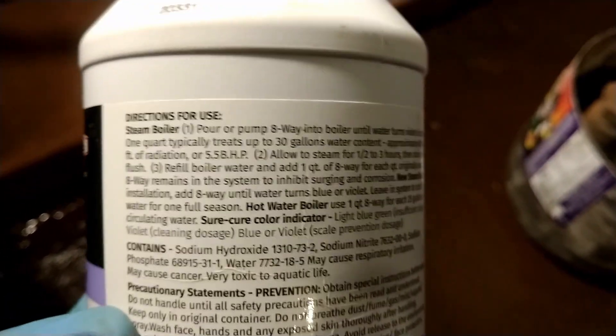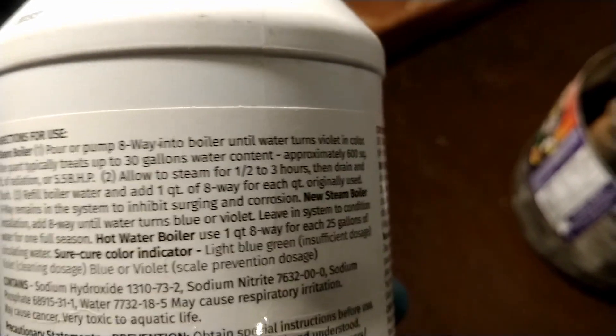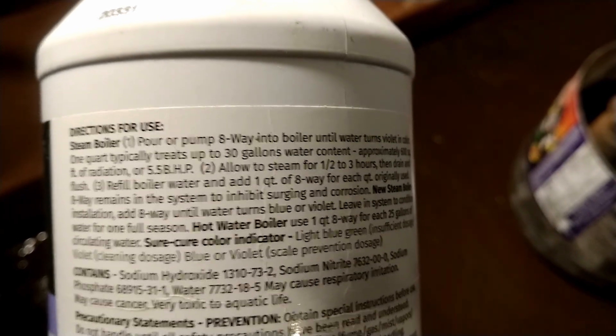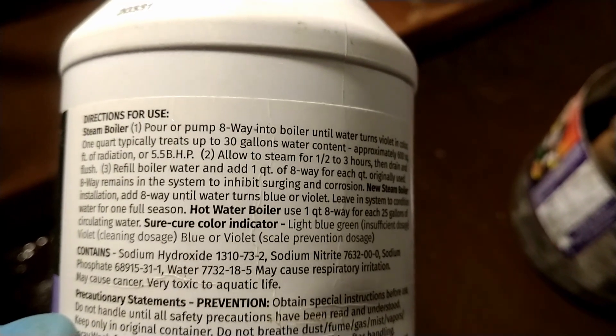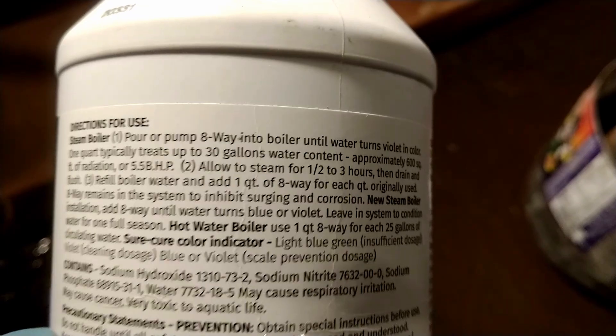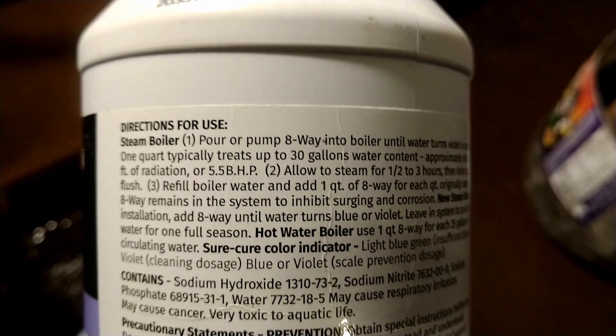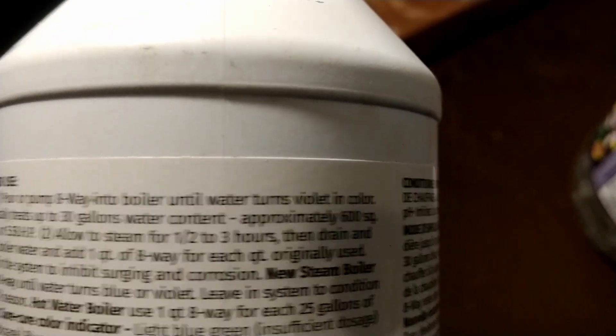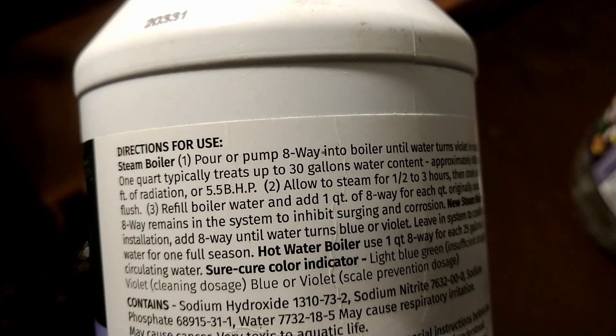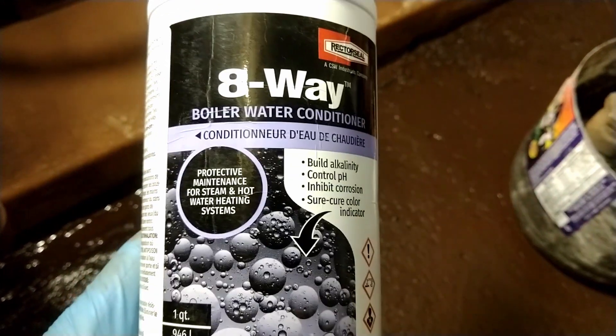You're supposed to pour the Eight-Way into the boiler until the water turns violet in color, then run the steam system for about 30 minutes to three hours until the water turns blue or violet, leaving the system to condition for one full season. You allow the steam to run for 1/2 to 3 hours, then drain and flush.